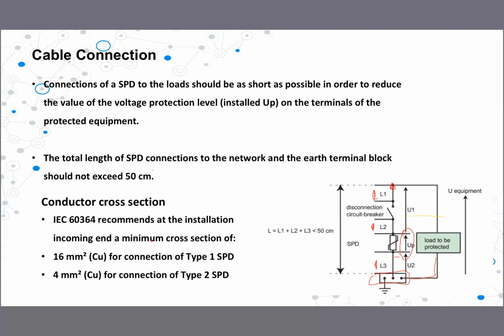So therefore, we can't get the required protection value if we increase the cable length, right? Our terminal load has a certain insulation level. If we increase this, then this part is also added into this, and then it exceeds the value here. Therefore, we need to limit it. It says less than 50 centimeters, meaning half a meter, right? You should connect the surge protector within 50 centimeters to the earth terminal and live conductor. Otherwise, your protection will not be effective, right?